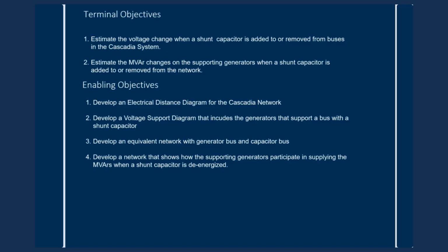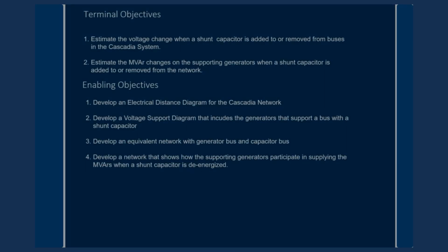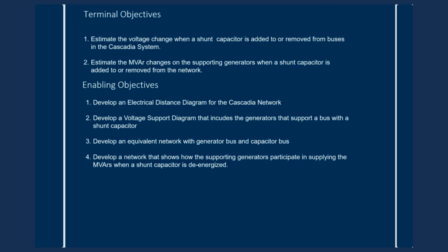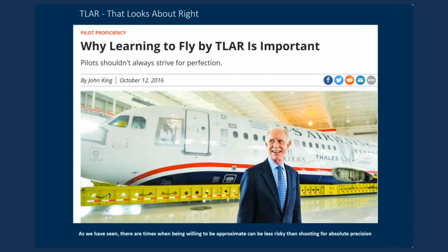The enabling objectives will include developing an electrical distance diagram for the Cascadia network, and then developing a voltage support diagram that includes just those generators that support a bus with a shunt capacitor. Then we will develop an equivalent network where there's just a single generator bus and capacitor bus, and based upon that network we can estimate the voltage change when the capacitor is added or removed. In addition, we'll develop a network that shows how the supporting generators participate in supplying the megavars when a shunt capacitor is de-energized. A recurring theme throughout these modules is TLAR.